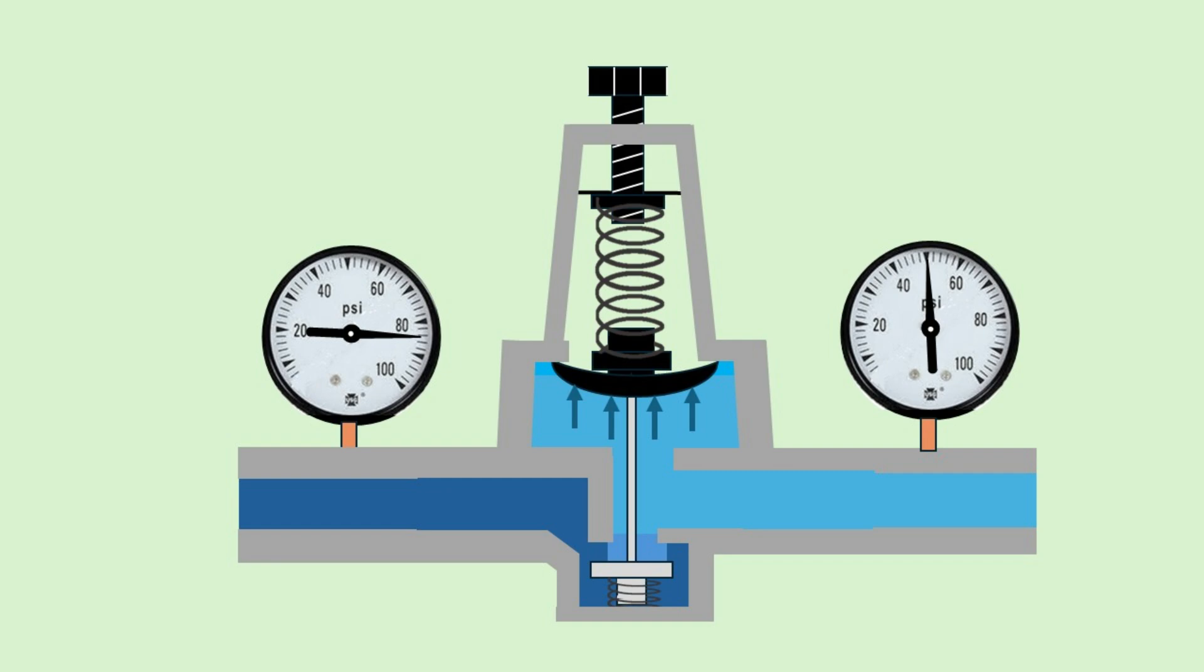Now let's look at what happens when the inlet pressure suddenly increases. Here, the inlet pressure suddenly jumps from 85 PSI to 110 PSI. Note, in reality, this happens instantly, but I'm showing it step by step to make it easier to follow. This higher pressure pushes against the diaphragm with more force. This causes the diaphragm to move upward slightly.